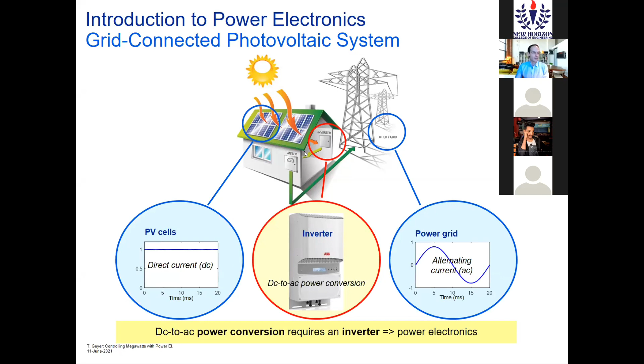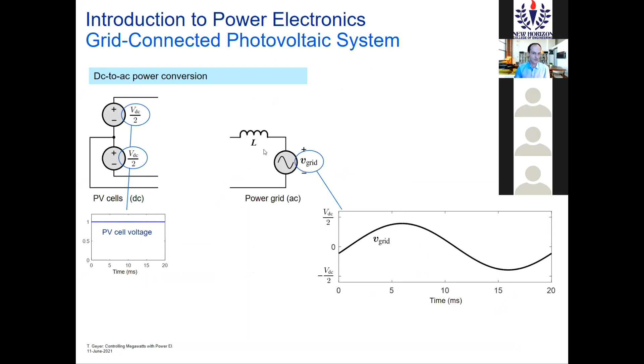Assume on the left-hand side you have two cells with a total DC link voltage of VDC, and on the right-hand side you have your grid voltage at 50 or 60 Hertz. You might have a grid impedance, which could be your distribution and transmission transformers. Then you want to control this current, and the current we feed into the grid ideally is in phase with the grid voltage, so we get power factor 1, maximizing active power transfer and minimizing reactive power.